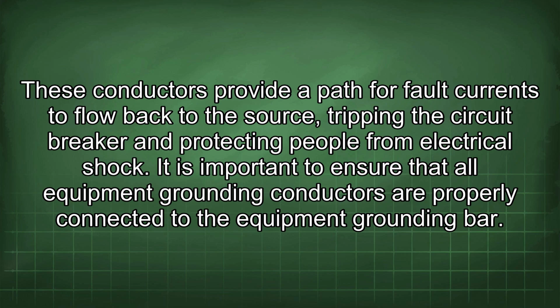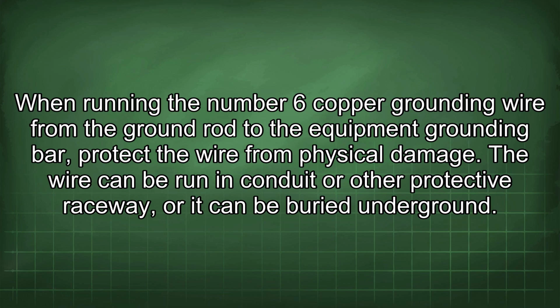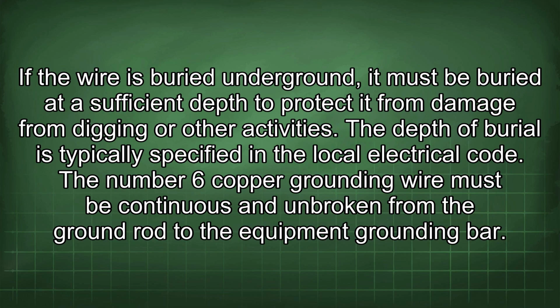grounding bar. When running the number 6 copper grounding wire from the ground rod to the equipment grounding bar, protect the wire from physical damage. The wire can be run in conduit or other protective raceway, or it can be buried underground. If the wire is buried underground, it must be buried at a sufficient depth to protect it from damage from digging or other activities. The depth of burial is typically specified in the local electrical code.